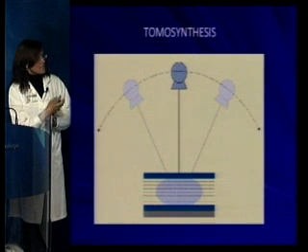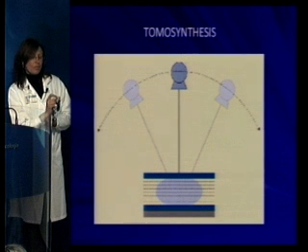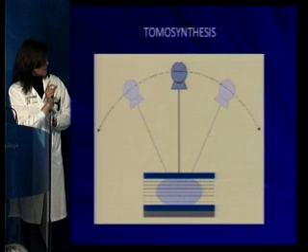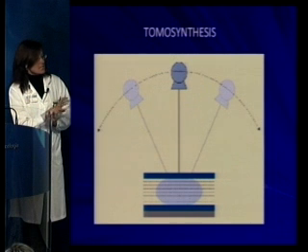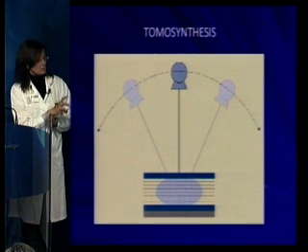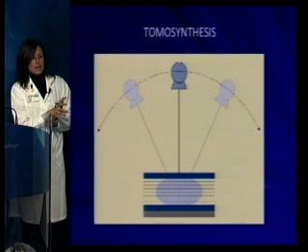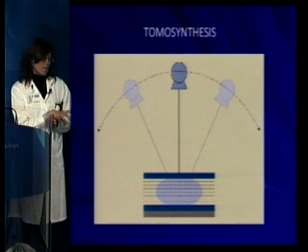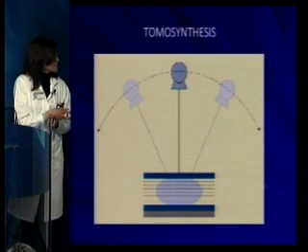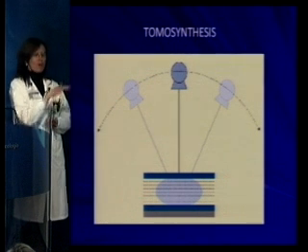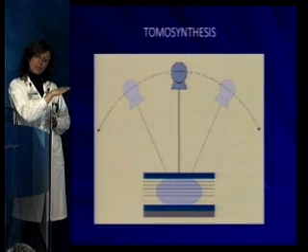We obtain a large number of very thin sections of the breast — thin images of the breast — and there is a mathematical algorithm, just like the same one we use in CT acquisition. We produce images taking information from every layer of the breast.